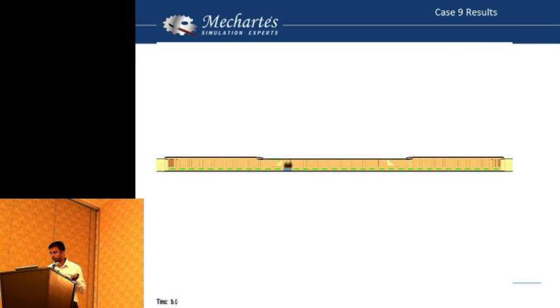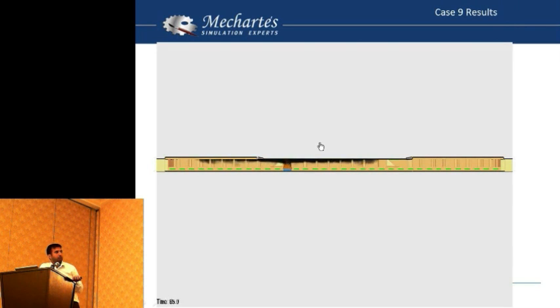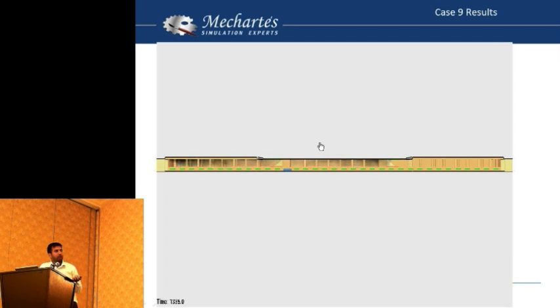Above 2.8 meters from the ground was the smoke layer height, and below that the visibility was quite good — apart from one corner area which was not of much concern, as not many people would be there. It took about 10 minutes for smoke to reach that area. This was a good design and was finally implemented in the metro.